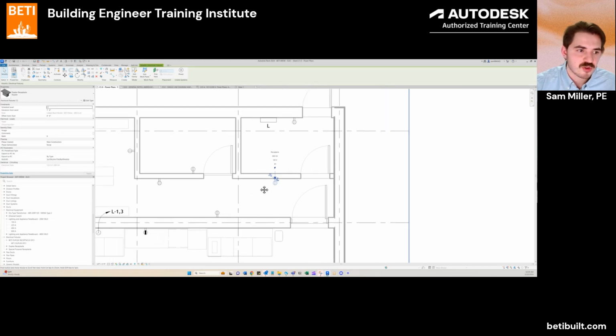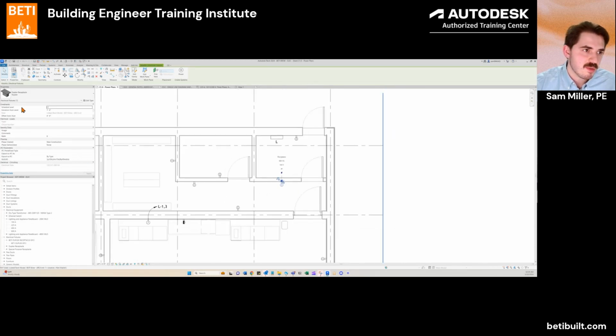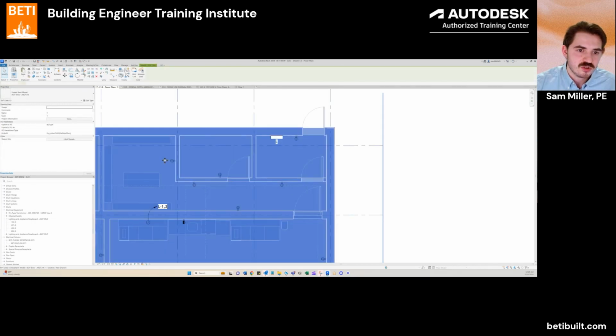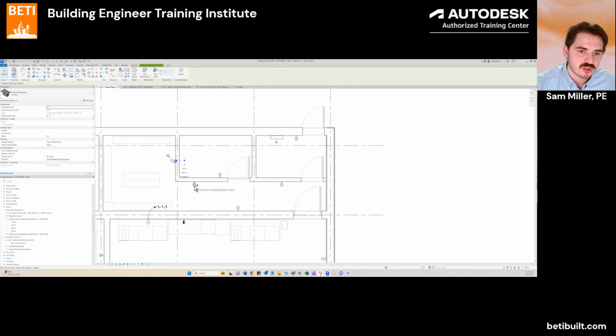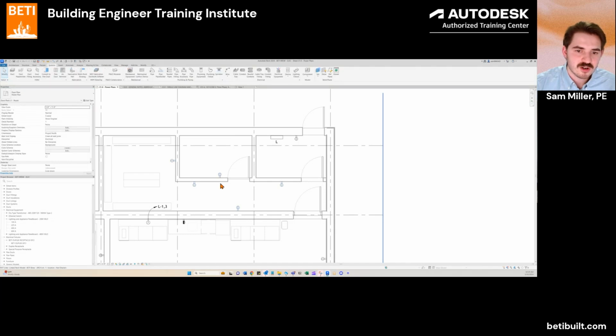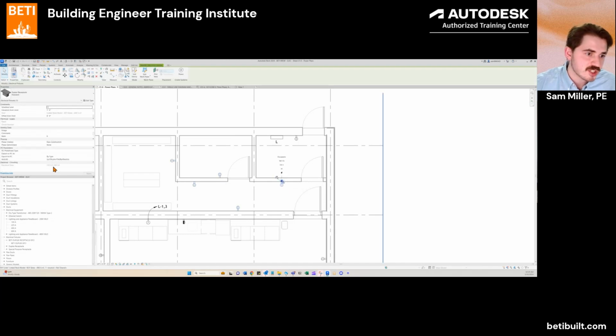I'll click this convenience receptacle. This looks like a mistake in my model because it says toaster - I don't want that, since it would bring it in at 500 VA. Let me check if the others are set this way too. Yes, these are all toaster, but they should be standard duplex receptacles. A quick way to fix this: click one, hold Control, click the other receptacles, go to the drop-down, and change them all to standard. Now when I click it, it shows 180 VA, which matches that section of code I mentioned earlier. Convenience receptacles are required by the NEC to be 180 VA, and Revit already knows that, which is why the standard was set this way.